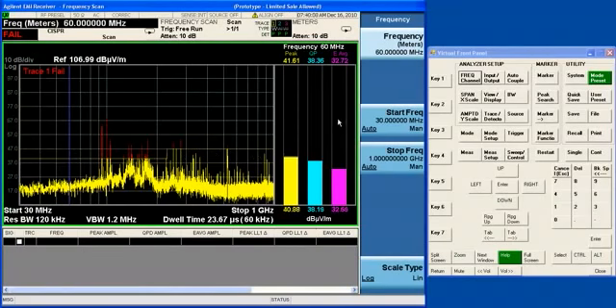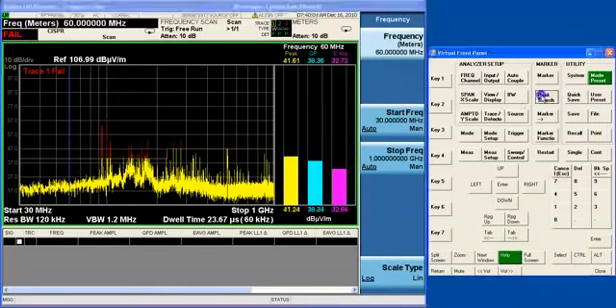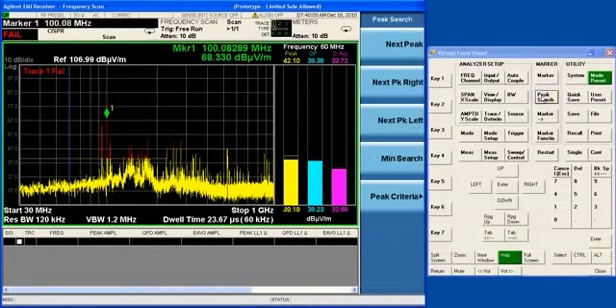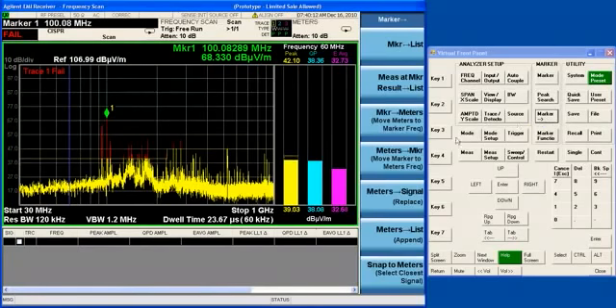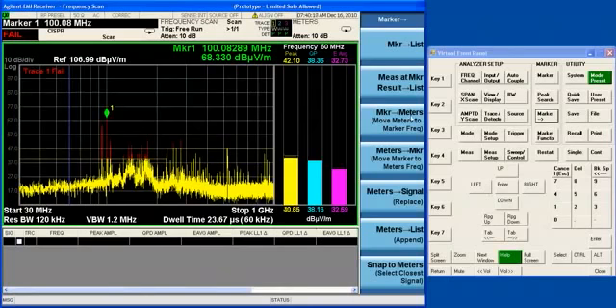I can actually do a peak search function to move the marker to the strongest signal on the display, and then I can move the marker frequency into the meters by doing a marker to meters function.